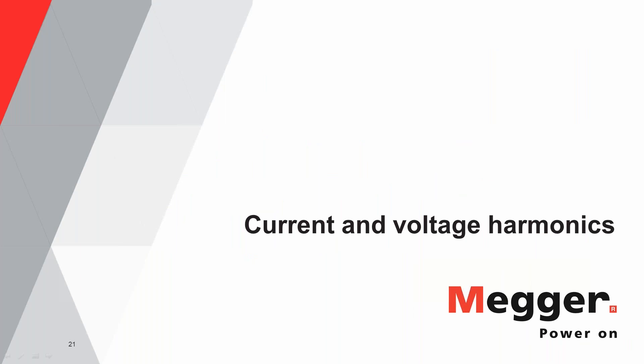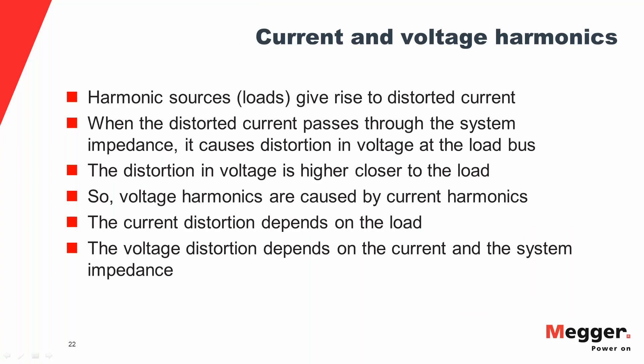Now let's look at current and voltage harmonics. Current harmonics are what we saw so far — the distorted current drawn by a nonlinear load. When that distorted current flows through the system impedance, it gives rise to voltage distortion. So voltage harmonics are caused by current harmonics. Current distortion depends solely on the load, but voltage distortion depends on both the current and the system impedance through which it passes.